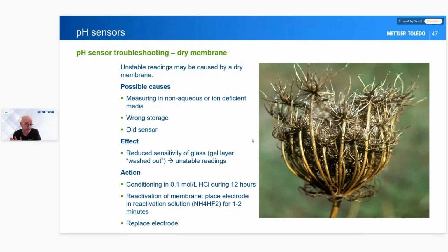So when we came at the beginning of this 1 to 3 years, it's generally around that gel layer. So if we have reduced sensitivity of glass and it's washed out and we have unstable readings, then what we can do is try and condition in hydrochloric acid. So 0.1 molar hydrochloric acid for 12 hours. That's a really good one for cleaning electrodes. And I would recommend, if I'm in a lab, running this conditioning once a month, whether your electrode's in good or bad condition, it just helps. It keeps that gel layer well hydrated and full of H+ ions. So my recommendation is condition once a month, whether your electrode is old or new or anything else.